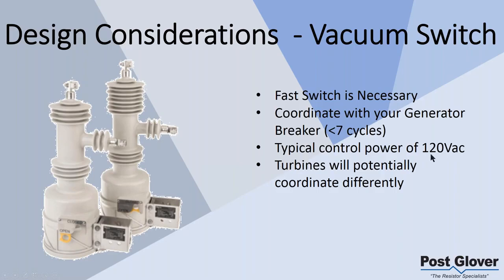Just as a note, what I've seen so far in my research, a lot of times you have control power of 120 volts for these medium voltage vacuum switches. So you're going to have to figure out a way to provide that. If you have turbines, don't assume that they're exactly the same as a generator, because we might have to coordinate them a little differently. So I just want to make a note. We're not going to go into details on that, but you probably want to do it more sequentially than you would with a generator.